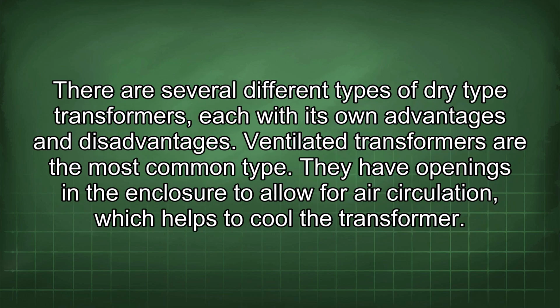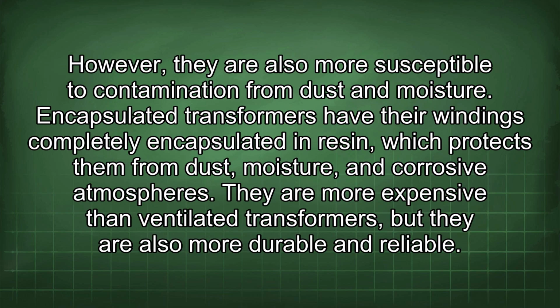There are several different types of dry-type transformers, each with its own advantages and disadvantages. Ventilated transformers are the most common type. They have openings in the enclosure to allow for air circulation, which helps to cool the transformer. However, they are also more susceptible to contamination from dust and moisture. Encapsulated transformers have their windings completely encapsulated in resin, which protects them from dust, moisture, and corrosive atmospheres. They are more expensive than ventilated transformers, but they are also more durable and reliable.